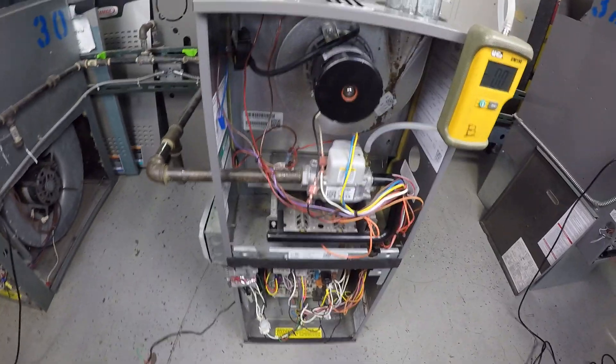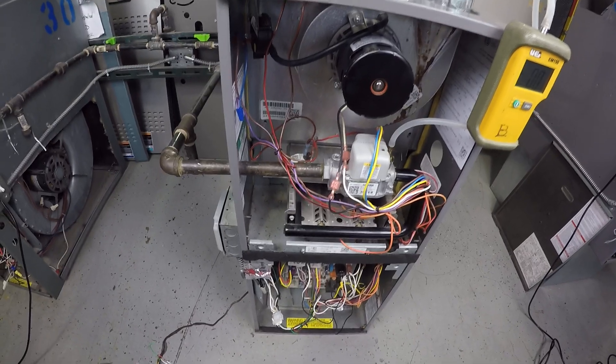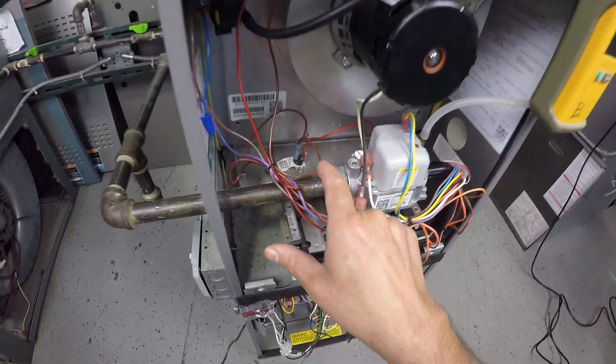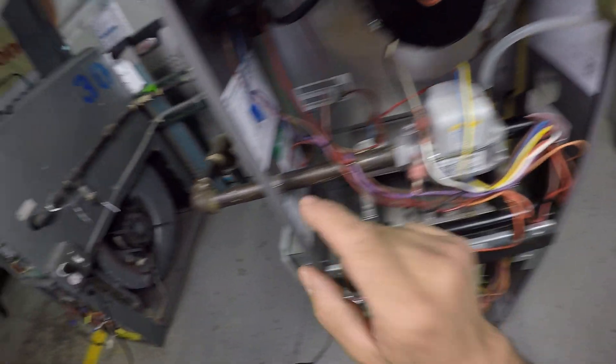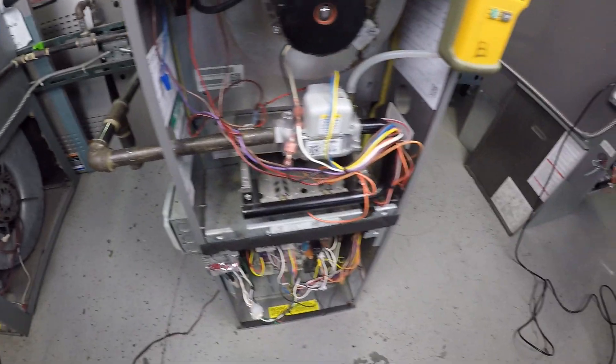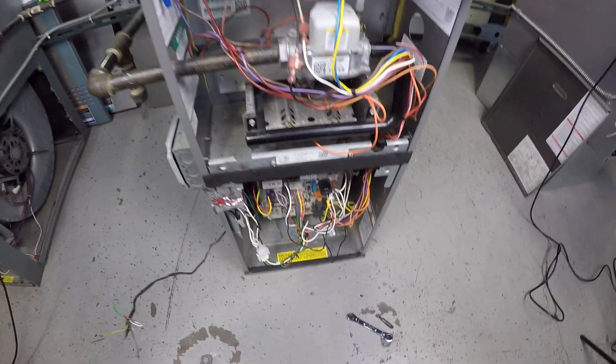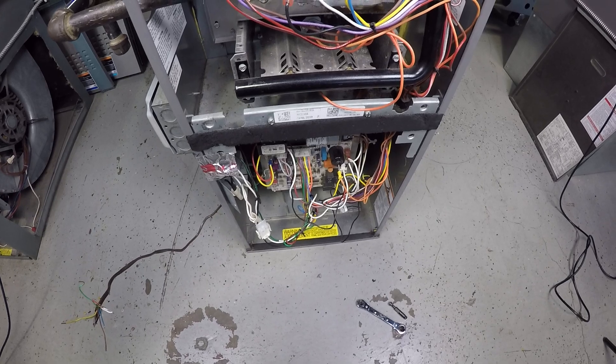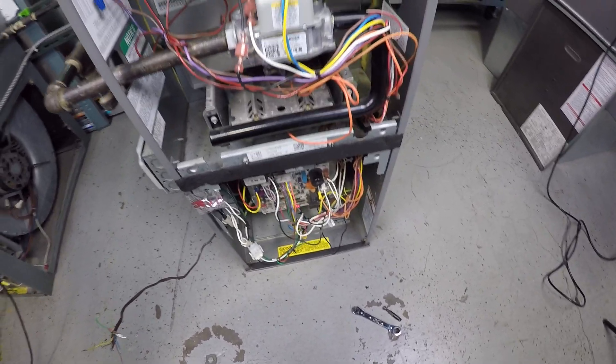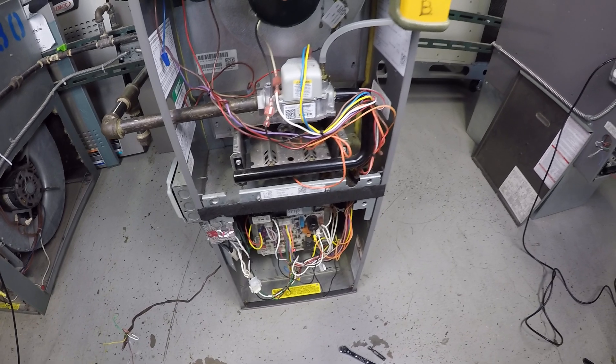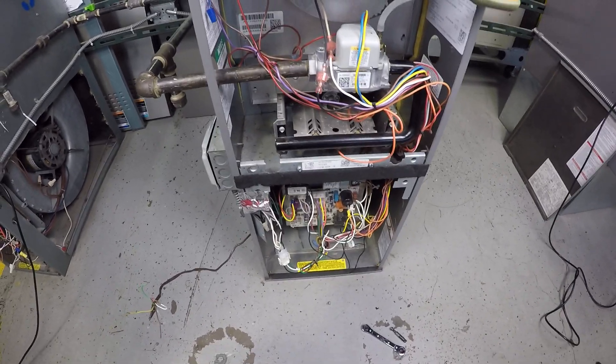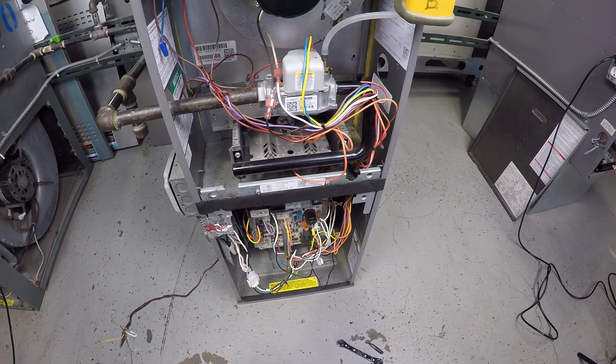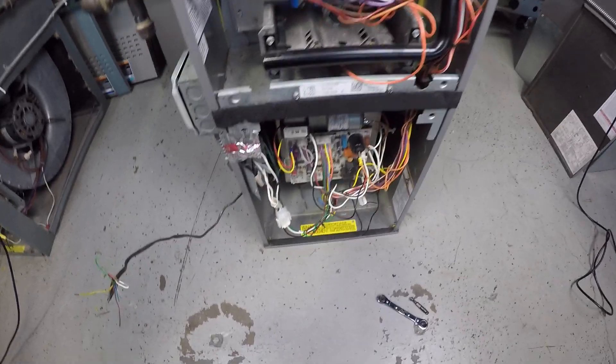And the furnace should be coming on. It's going to go through a sequence operation. Thermostat, inducer motor, safeties, rollout switches, limit switch up there. And, it should start any second. It takes about 10, 11 seconds. Just wait for that flame. There you go. You hear the spark.